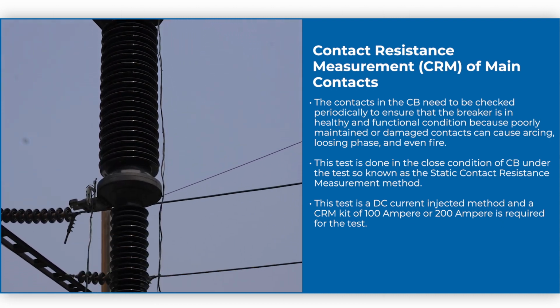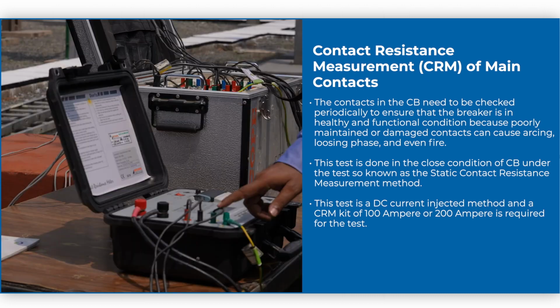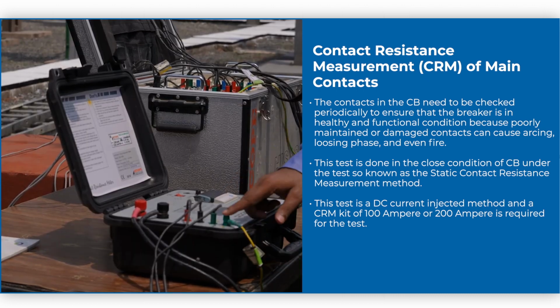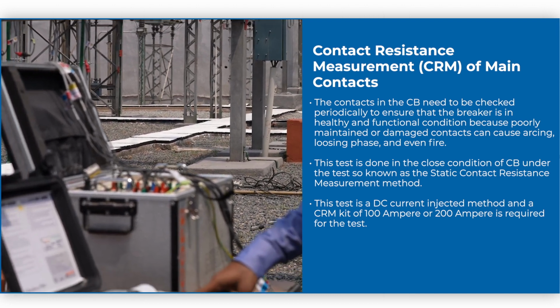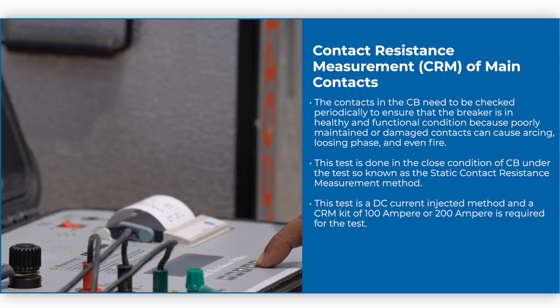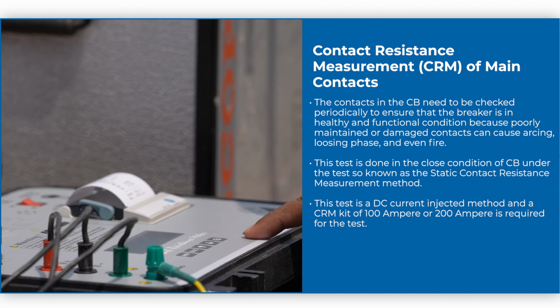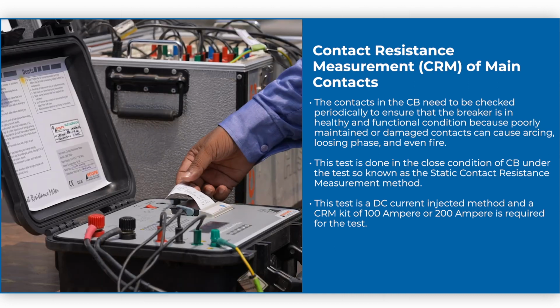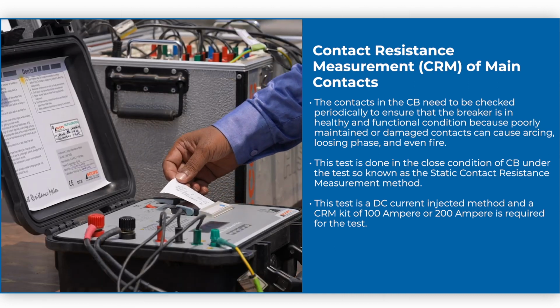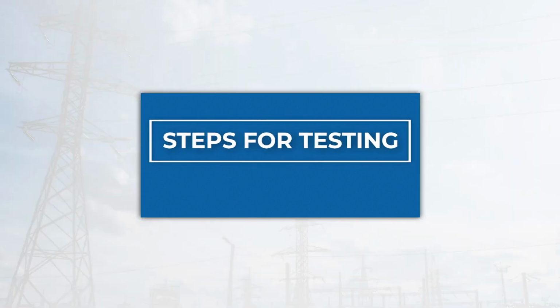This test is done in the closed condition of the CB under test, so it is known as the static contact resistance measurement method. This test is a DC current injection method, and a CRM kit of 100 ampere or 200 ampere is required for the test. Steps for testing.